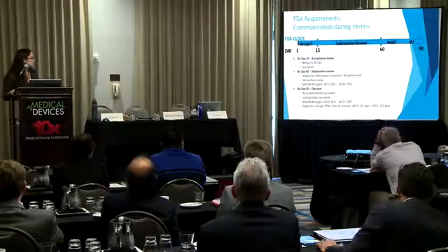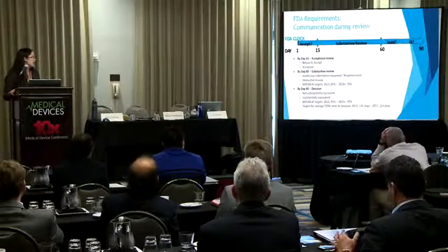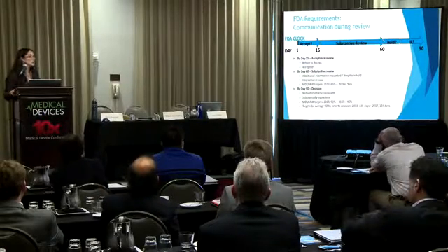And the total time to decision, the target that FDA has for 2017 is 124 days. So a lot of clients ask me, how long is this going to take? Even if we're put on hold, you have 180 days to answer additional information questions. So it's really up to you. But FDA is saying, even with the questions that we're asking, we're hoping to have 124 days be the entire review clock.